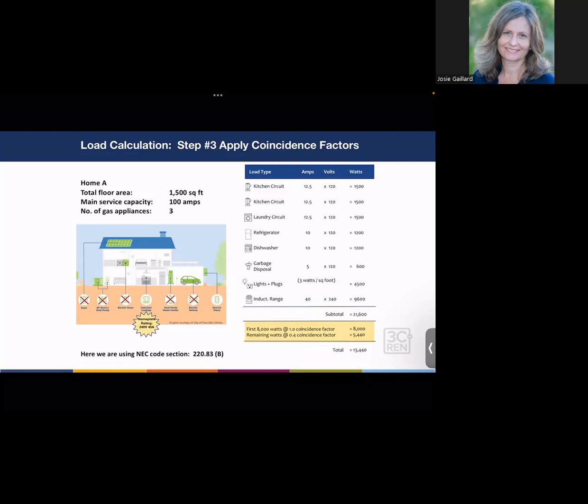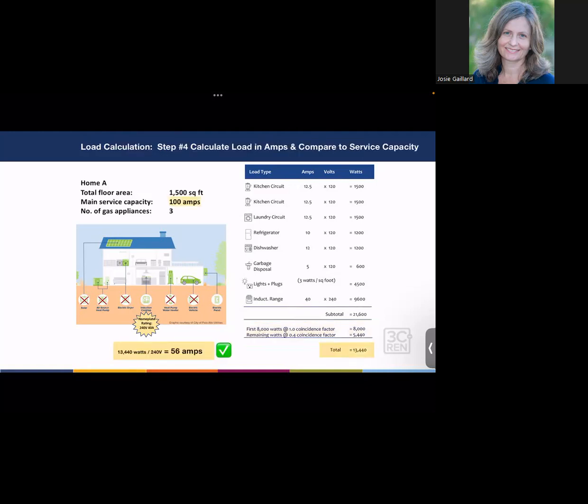So we apply 0.4 to the remaining, I guess it was about 13,600 watts, and we get 5,440 watts. We add 8,000 to 5,440 to get 13,440 watts, assumed for the home with the new induction range. Now with that 13,440, we need to divide by 240 volts, which is the voltage of the whole home. So that's the voltage coming in through that service line. So we divide the total power required to run this home by 240, and we get 56 amps.